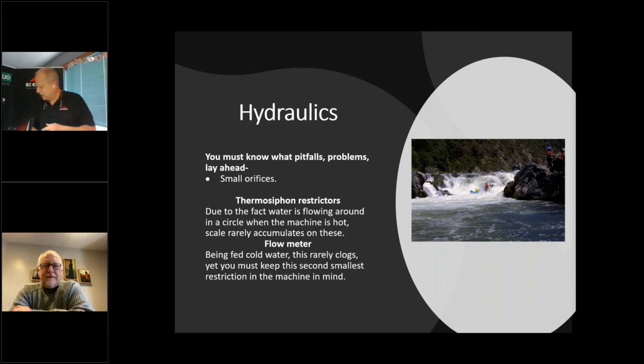Inside the system, we have thermosiphon restrictors and the flow meter. Now, on a thermosiphon machine, this is just a small one group tank. We take water from the heat exchanger and flow it up to the group, and then we take the tube on the other side for this type of machine and flow it to the bottom. The issue there is, even though it's like the third smallest restrictor in the machine, it doesn't have a problem because water is constantly flowing while we're hot. As long as we're idling the machine, the water is moving, and that's not an issue.